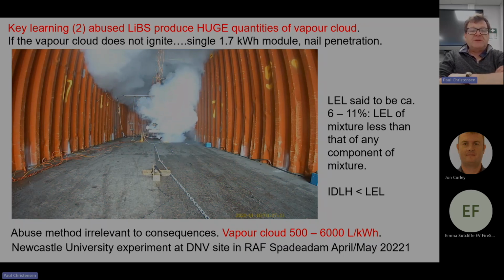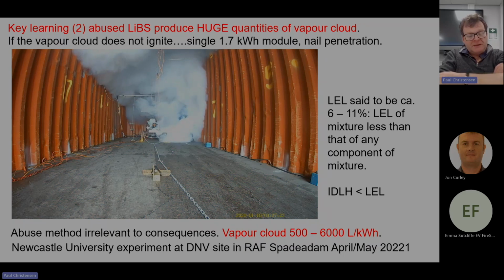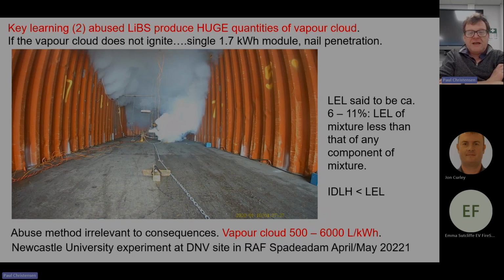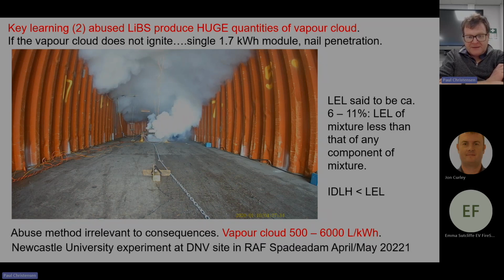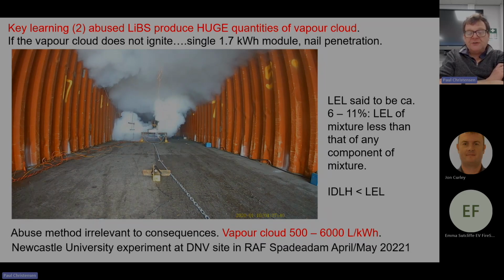Now, the lower explosion limit is between 6 to 11%, depending on the chemistry of the battery and other factors. But the immediate danger to life and health is much, much lower than that. And the key point here is that red sentence: 500 to 6,000 litres per kilowatt hour. So for a 100 kilowatt hour car, you're looking at 50,000 to 600,000 litres of toxic and explosive gas.